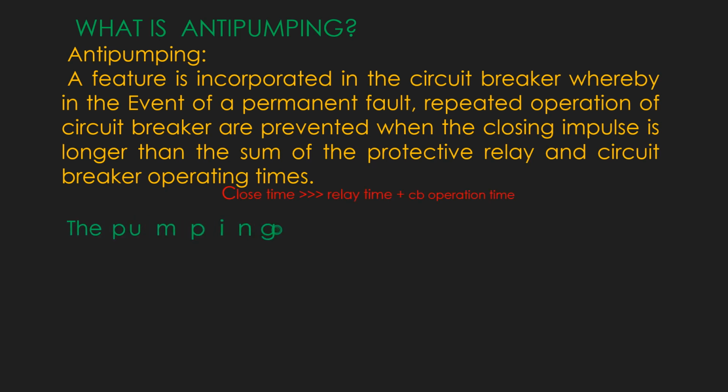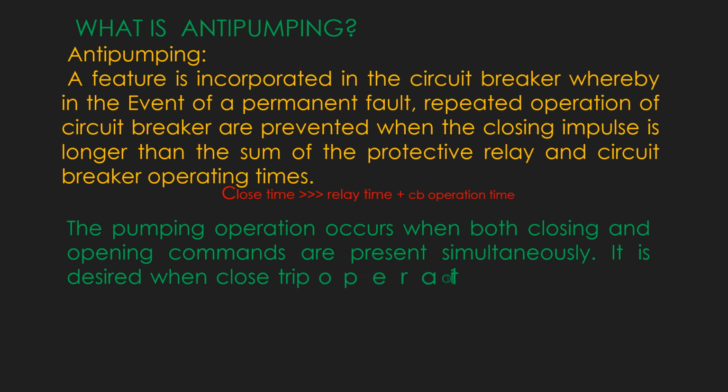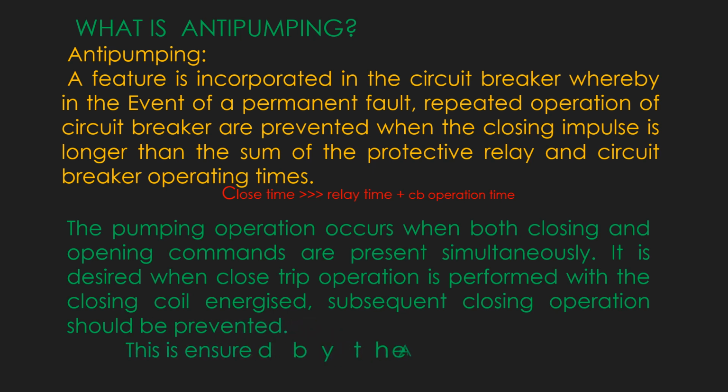The pumping operation occurs when both closing and opening commands are present simultaneously. It is desired that when a close-trip operation is performed with the closing coil energized, the subsequent closing operation should be prevented. This is ensured by the anti-pumping device.